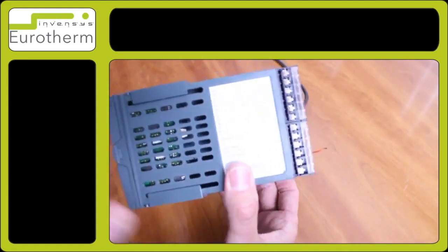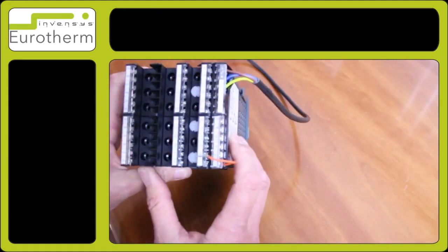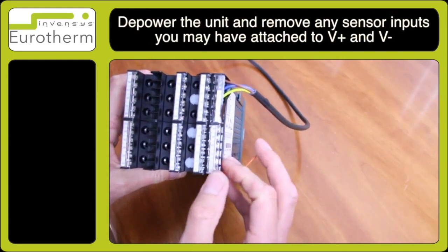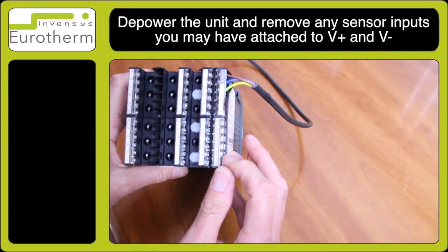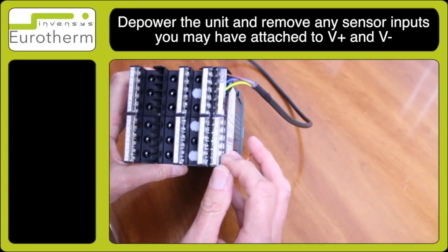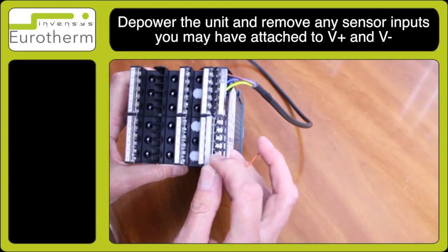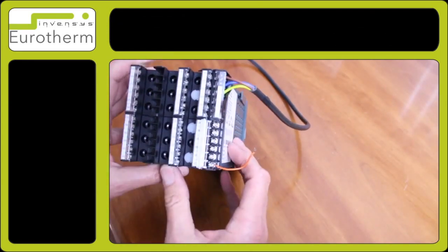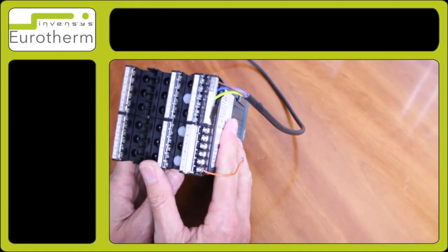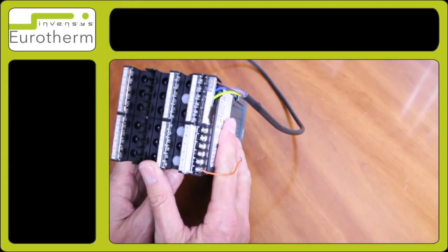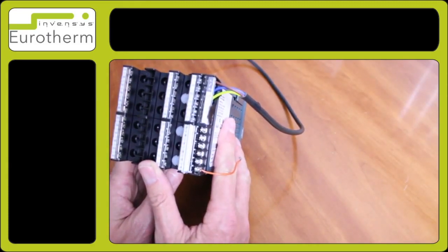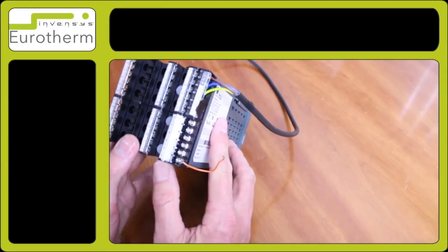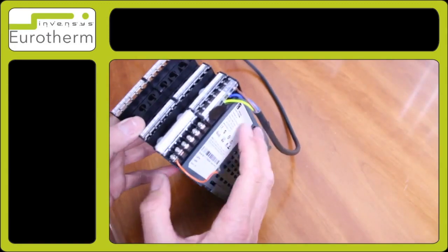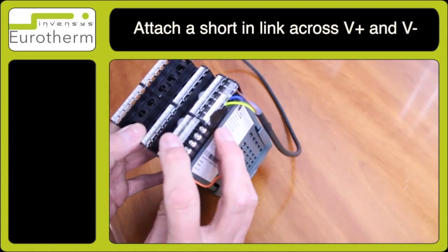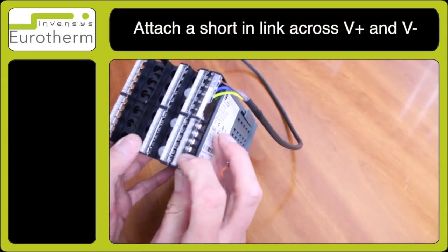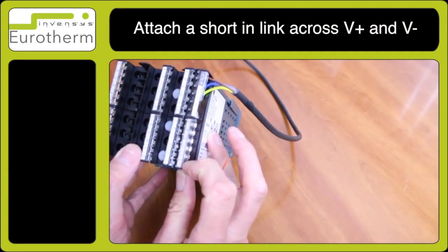Turn the instrument, or go to the back of the instrument, and observe V plus and V minus. This is where your sensor input wires will be. Remove those sensor input wires and take note of the position of the wires, as one is positive and one is negative. Use a shorting link and put a shorting link between V plus and V minus.